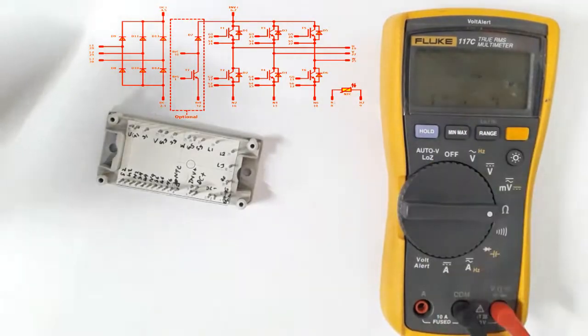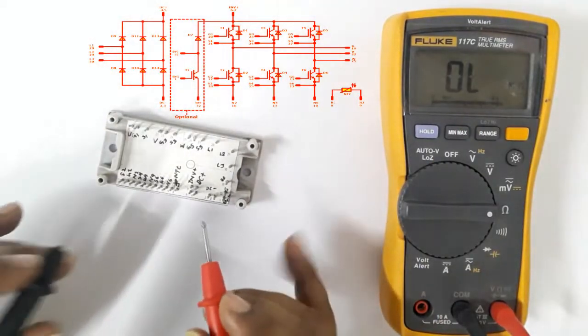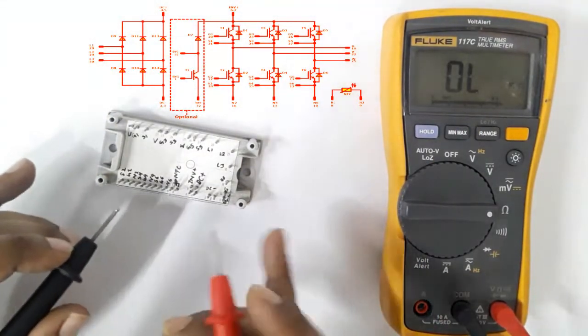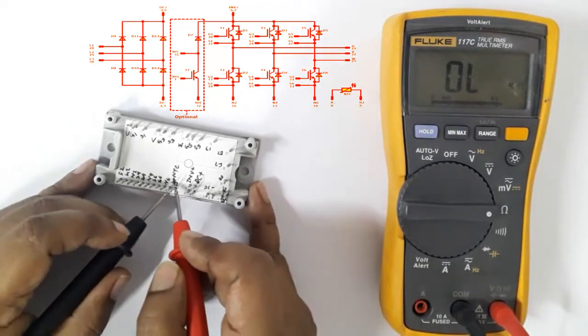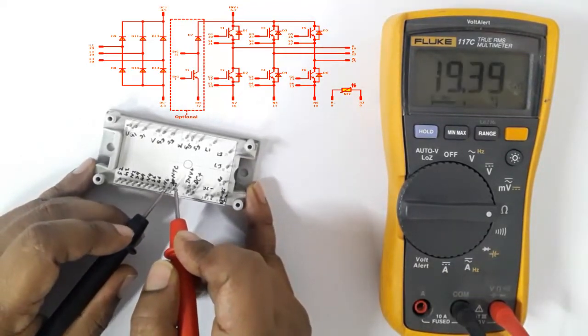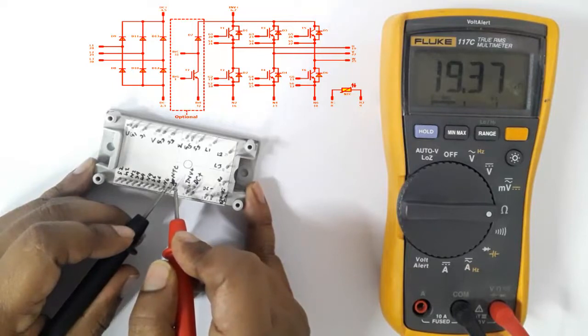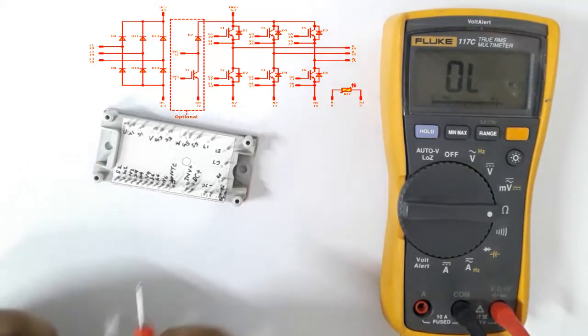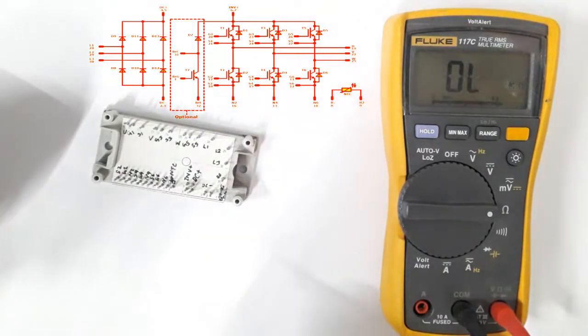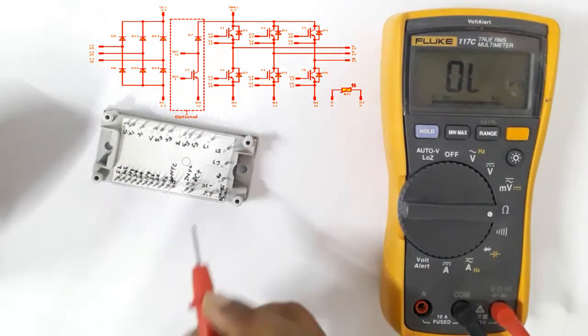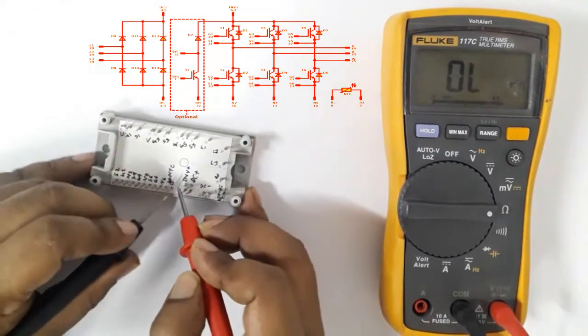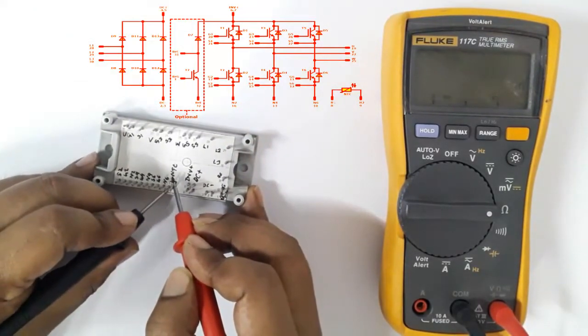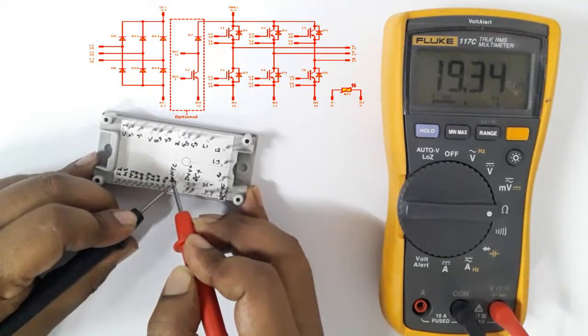Now we want to test NTC terminals 9 and 8. For NTC testing, about 19.37 kilo ohms. This one is used for NTC, negative temperature coefficient purpose. It's used in IGBT. So terminals 9 and 8 for NTC, about 19.35 kilo ohms.